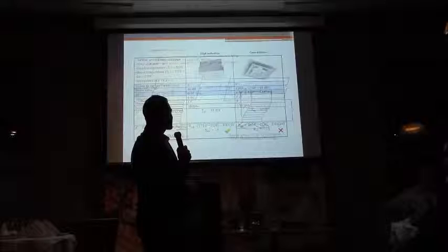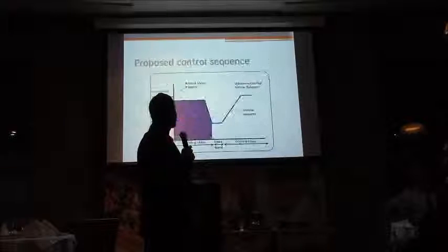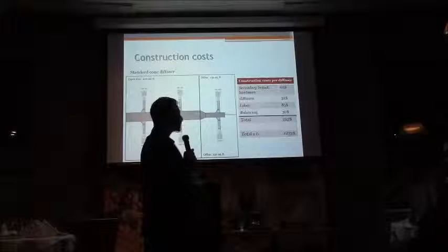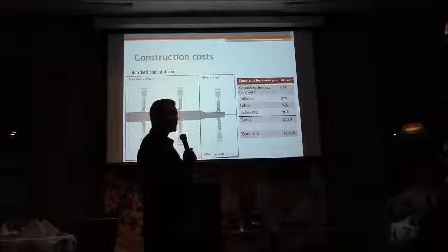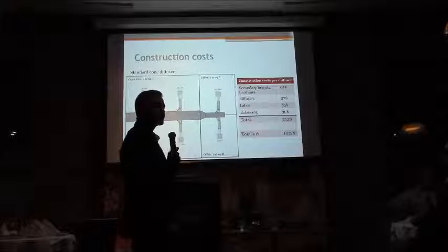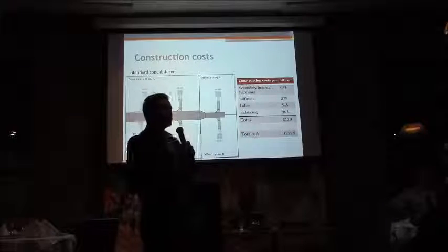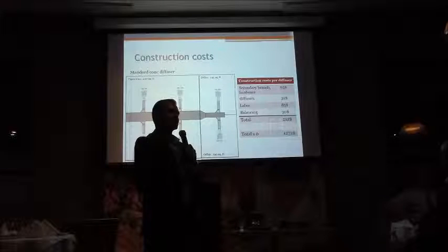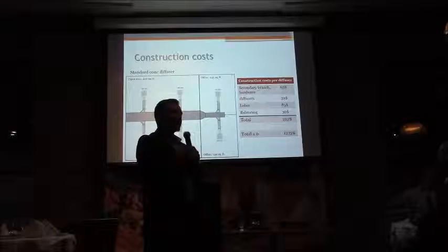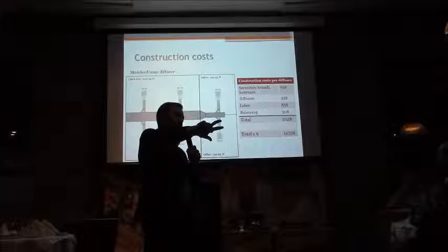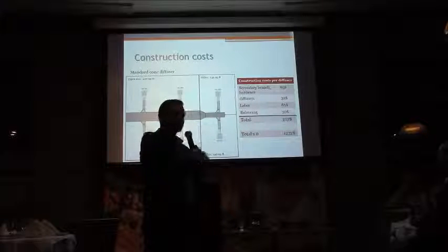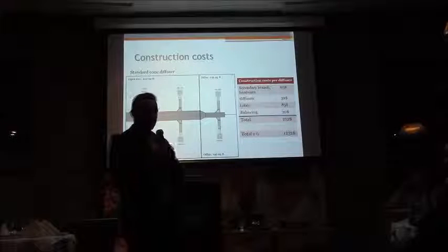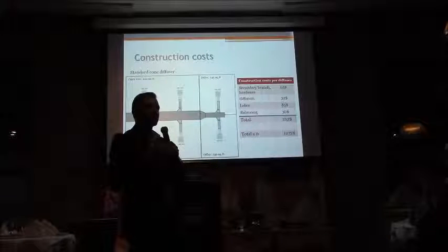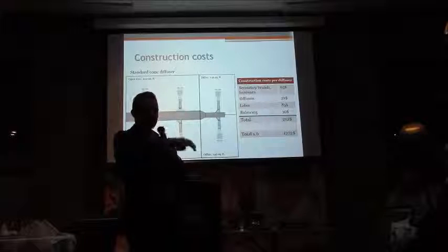On that demonstration of the layout, we went from 6 diffusers with the standard cones down to 4. How were you able to go from 4 to 2 in the open area? Is that because of the better distribution or better airflow diffusion? The way we mostly design our ventilation systems is we try to limit the amount of CFMs per diffuser. I rarely see more than 200 CFMs per diffuser, mostly because with cone diffusers, you're connecting your flexible duct straight into the inlet. So that adds sound, it adds static pressure, it affects your throw pattern. To compensate for that, we reduce the amount of CFM per diffuser to minimize all that turbulence effect. And you still have effective distribution.